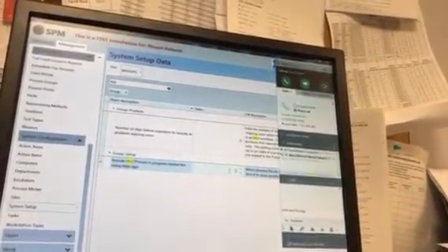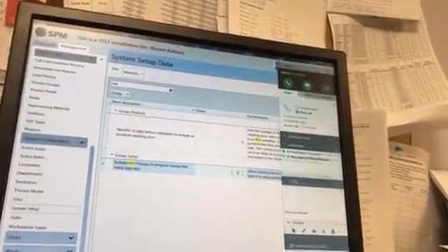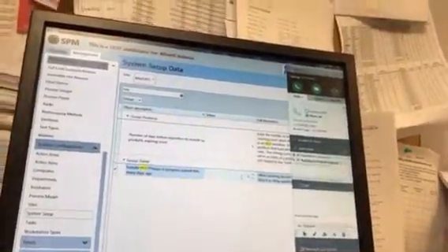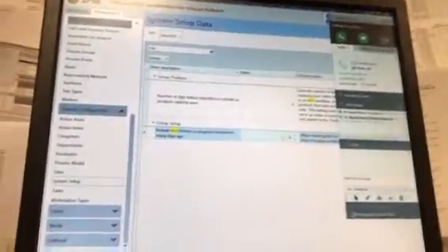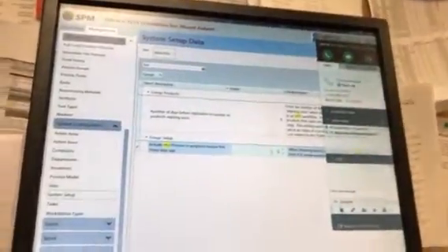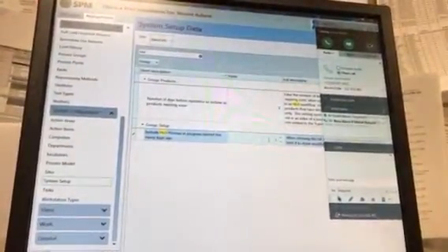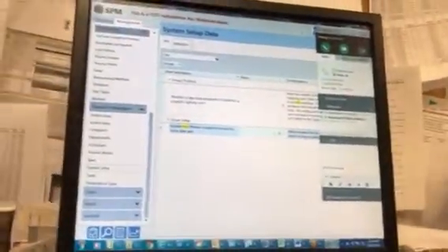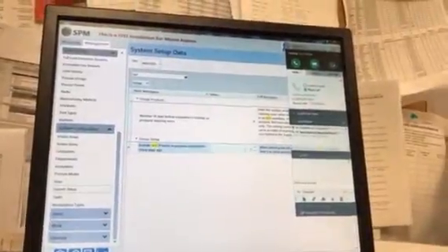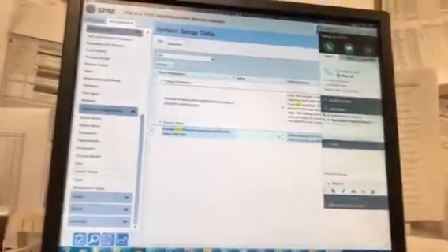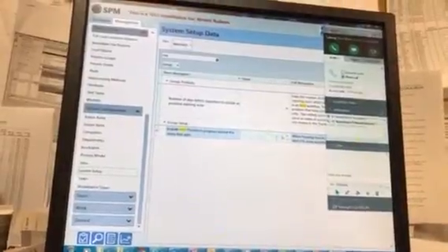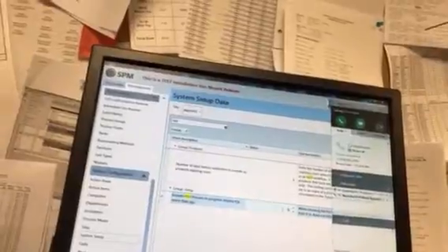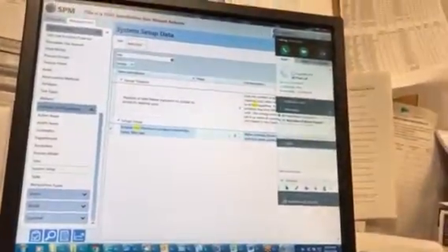Then the other mode of that screen, and we'll show you that in a second, is things expiring soon. And so you'll be able to see, for example, anything in your ancillary cart that is already expired or is about to expire. If nobody's come and picked it up yet, and this one isn't one you use as often, it's been sitting on your ancillary cart for 8 days, well, now somebody needs to go and run it through the System 1E again because it's expired now.